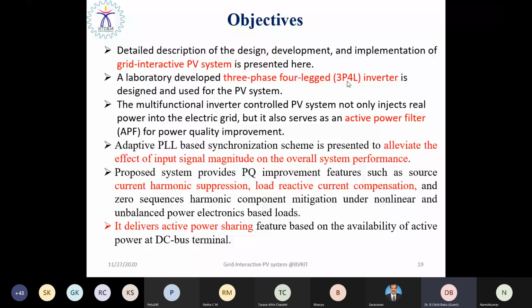That includes controllable active and reactive power into the utility grid, and it also serves as an active power filter for power quality. Whenever you connect a nonlinear load at a point of common coupling, it interacts with the grid source and the grid current is distorted. Distorted grid current degrades the power quality norms, and if any additional loads are connected, it also affects the performance. So we have to mitigate power quality problems and the lower order harmonics present in the grid current whenever a non-linear unbalanced load is connected at the point of common coupling, right?